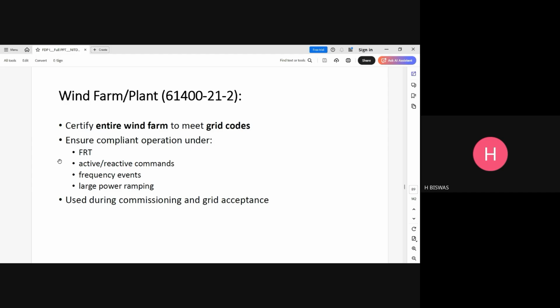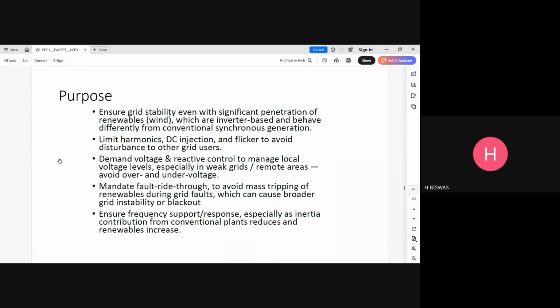So certify the entire wind farm to meet the grid code, ensure compliant operation, a requirement used during commissioning and, of course, grid acceptance. The purpose is to ensure grid stability even with significant penetration of renewables, which are inverter-based and behave differently than the conventional ones. Limit harmonics, DC injection, and flicker to avoid disturbance to the grid user. Demand voltage and reactive control to manage local voltage levels. Mandate FRT to avoid mass tripping of renewables during grid faults, which can cause broader grid instability or, in the worst case, could possibly cause a blackout. Ensure frequency support or response, especially as inertia contribution from conventional plants reduces and renewables increase.